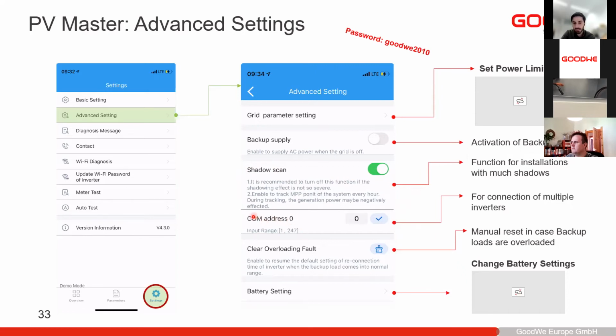The COM address here is only in case you want to connect multiple inverters in parallel to the SEC1000. Then you need to assign them to a specific COM address, and that you do here. Every inverter needs to have a unique address.